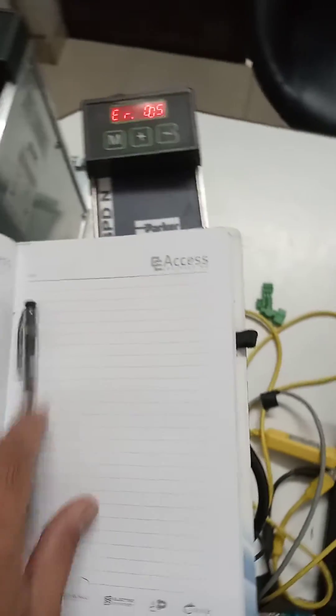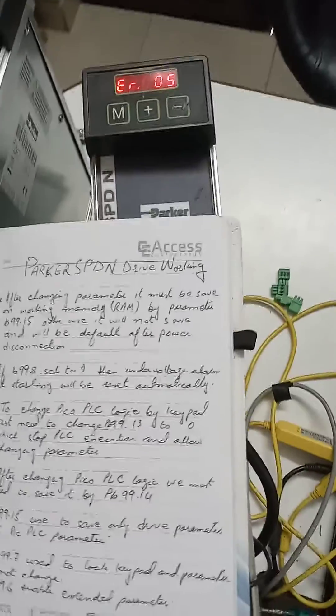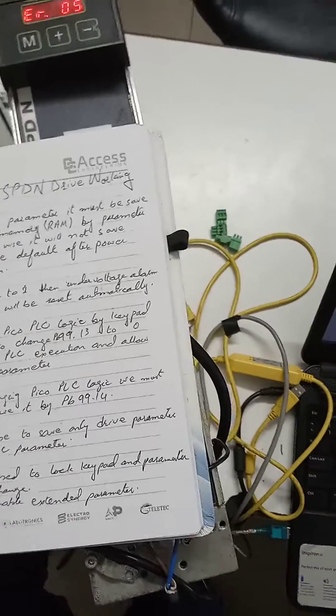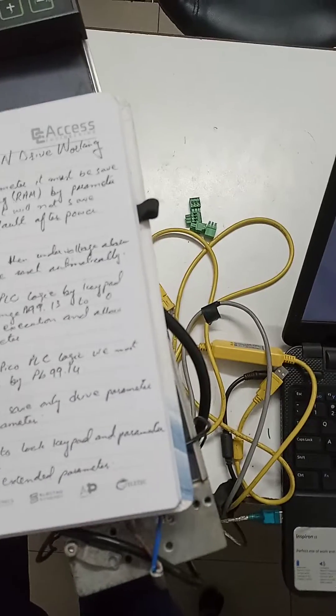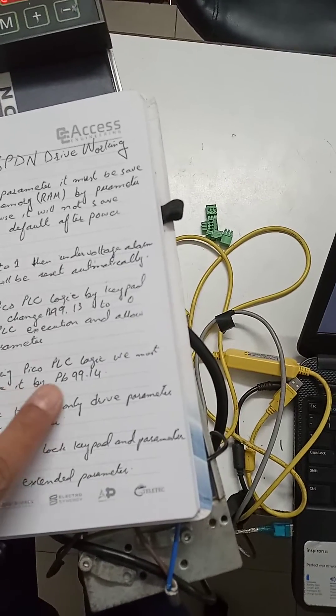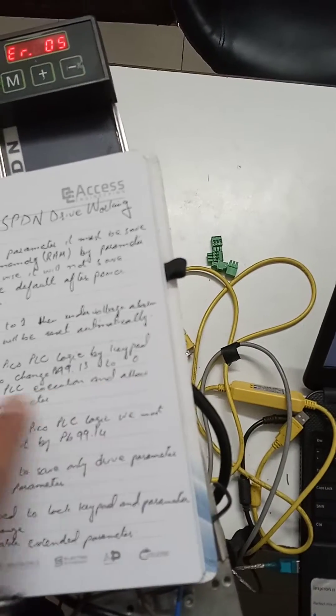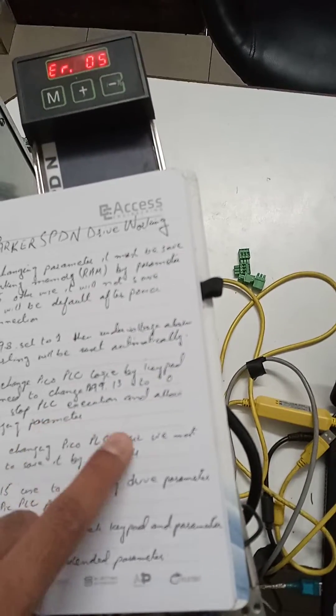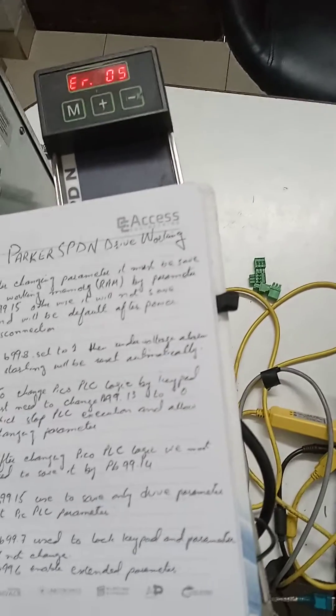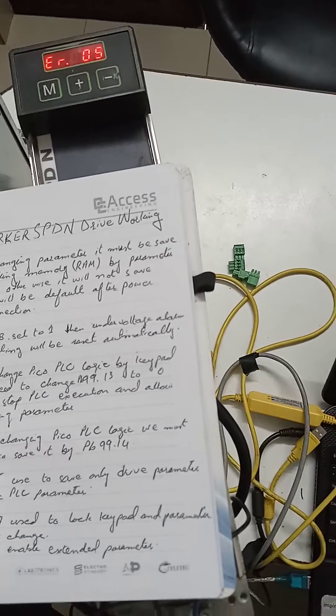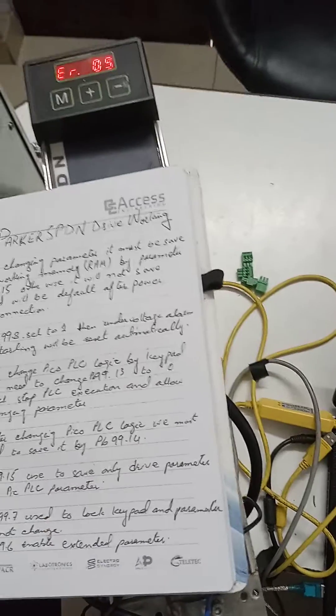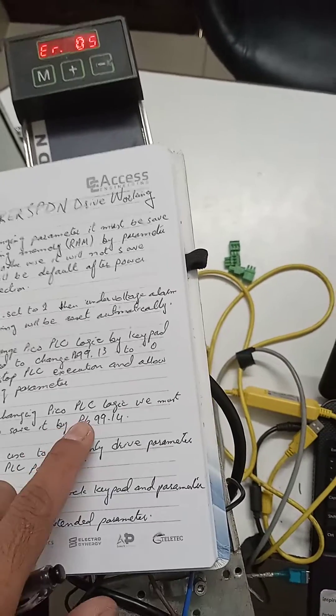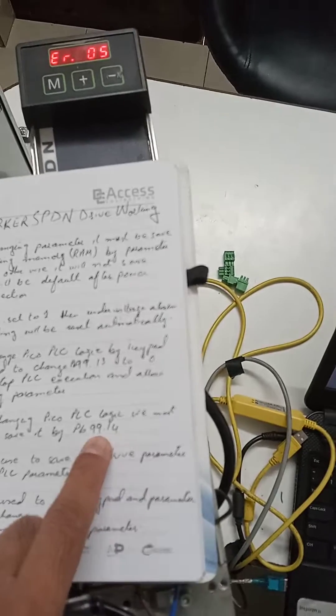If we want to change the pico PLC logic, first we need to set PB99.13 to 0, which actually stops the PLC execution and allows us to change the PLC logic. After changing PLC logic, we need to save it, which can be done by parameter PB99.14.